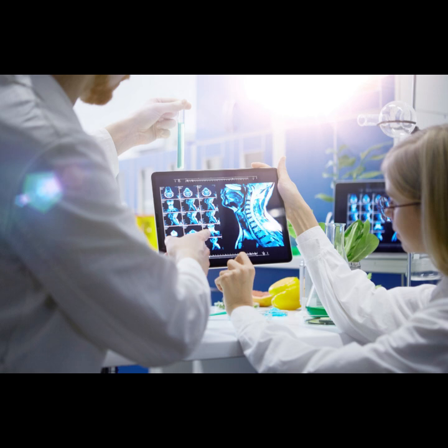If you were to, say, lose a chunk of data from K-space, you wouldn't lose a corresponding chunk of the image. Instead, the entire image might become slightly blurred or have some artifacts, but you'd still see the whole structure. Wow. This inherent redundancy, this non-local nature, is precisely why modern techniques like parallel imaging and compressed sensing work. They intentionally don't sample all of K-space. They grab strategic bits and rely on that holographic property and clever math to reconstruct the full image anyway. It saves a huge amount of time.